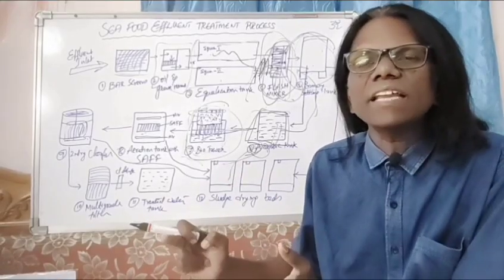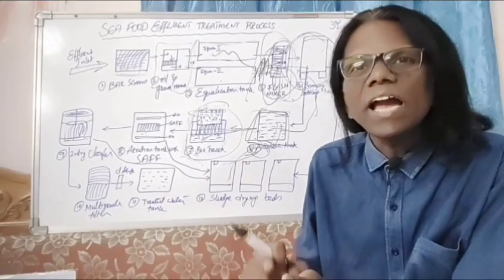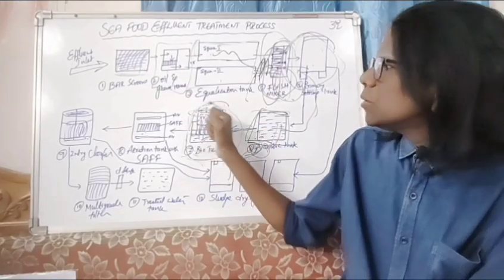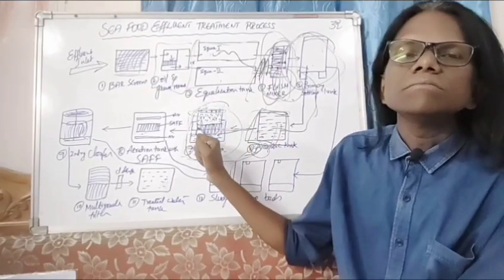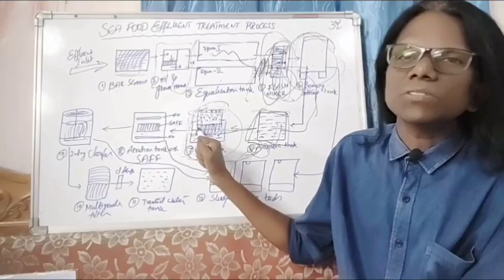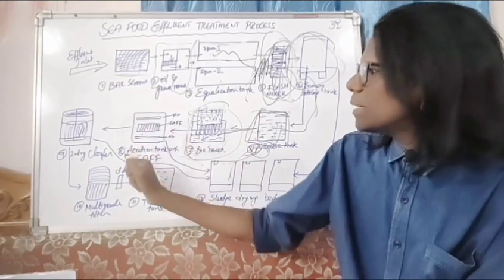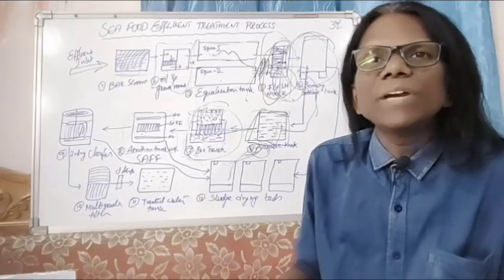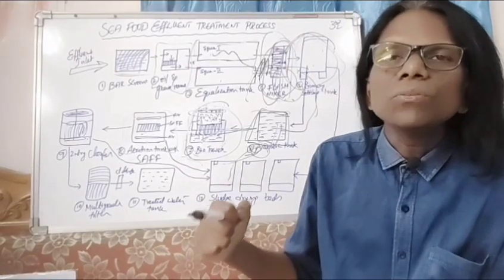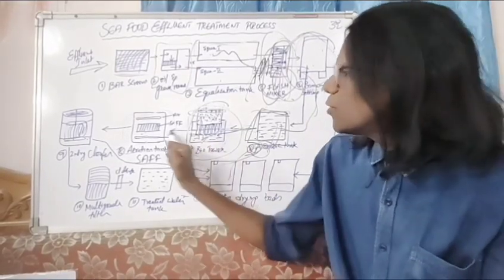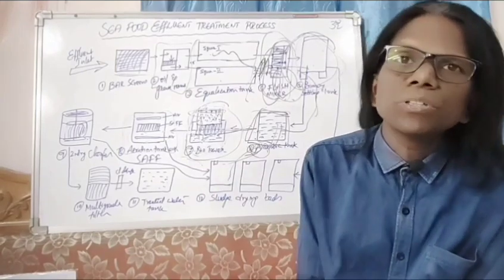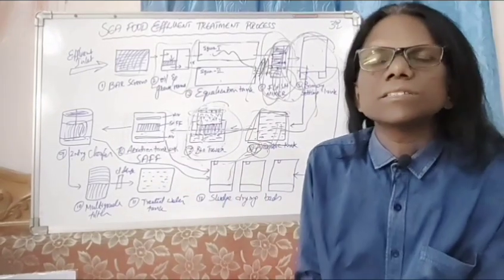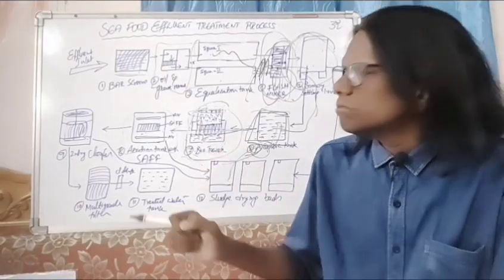You have to mix the jaggery in water with urea and DAP and pass it through the feed pump, which will give feed to the microbial flora during lengthy shutdowns. In the same way, you have to apply urea, DAP and jaggery to the aeration tank also. If there is no feed flow or no effluent flow for more than a week or more than 10 days, then the entire biological degradation system will deteriorate.